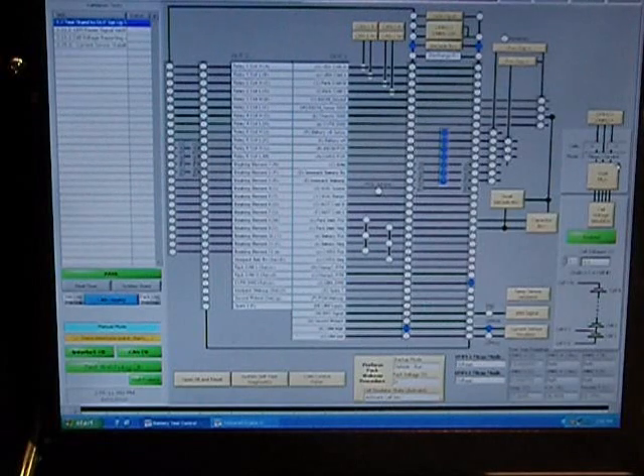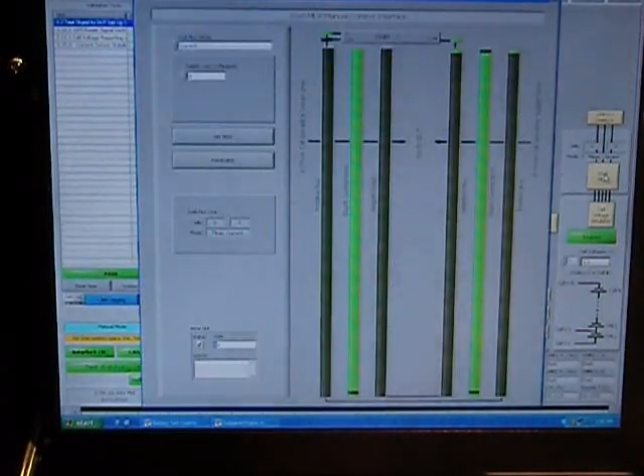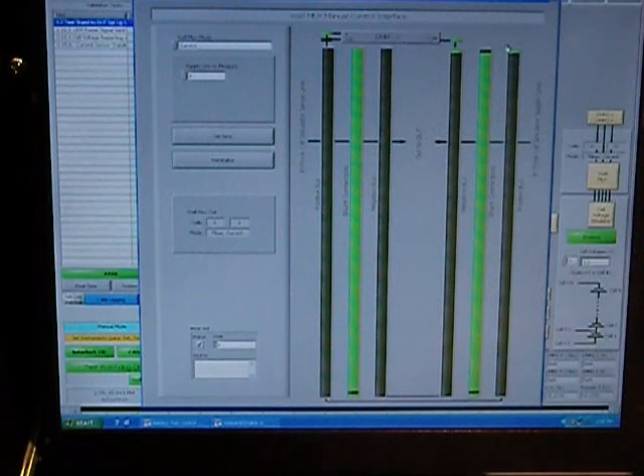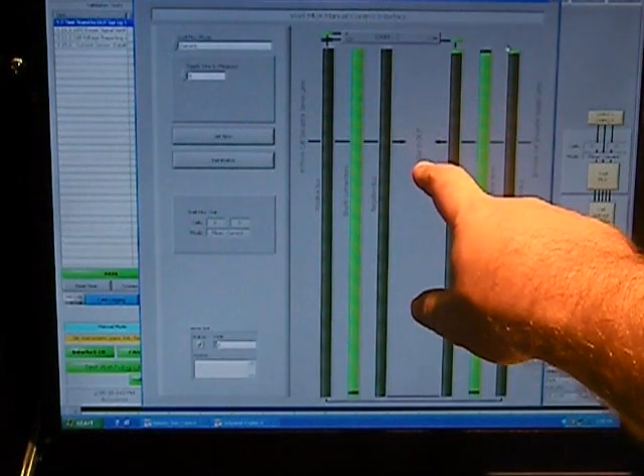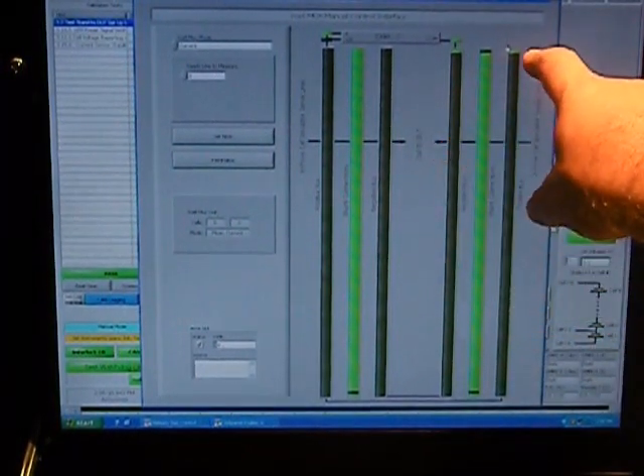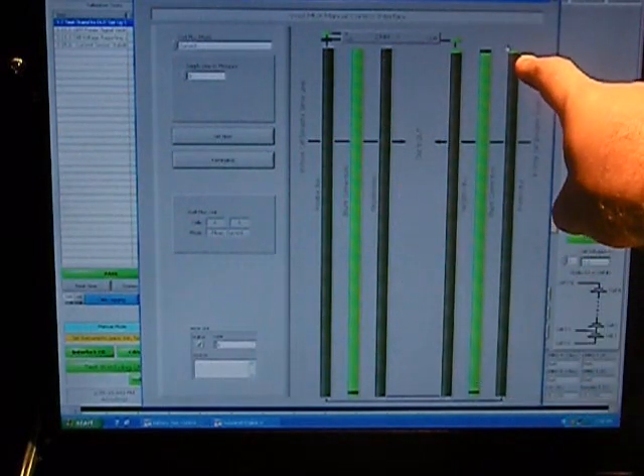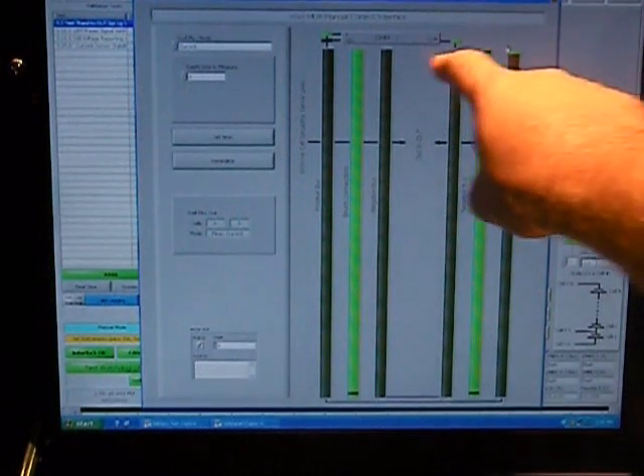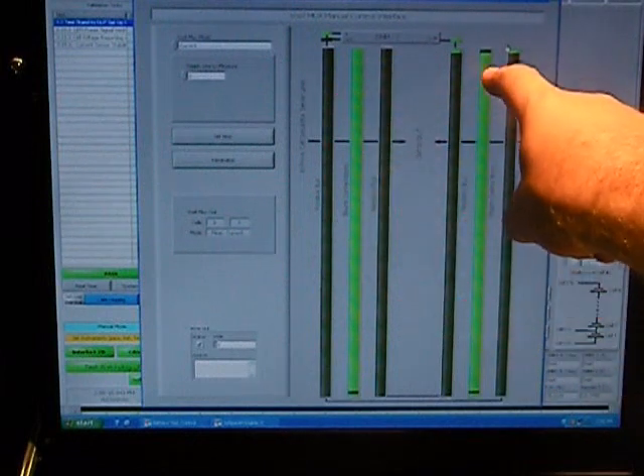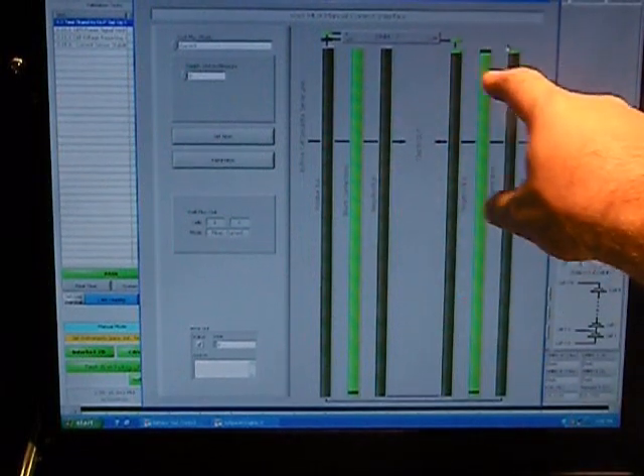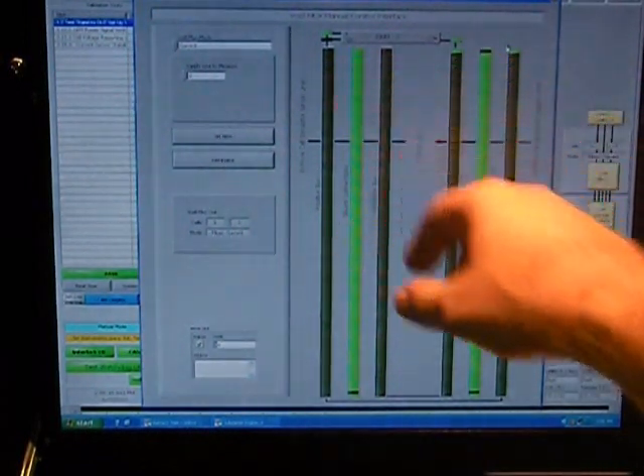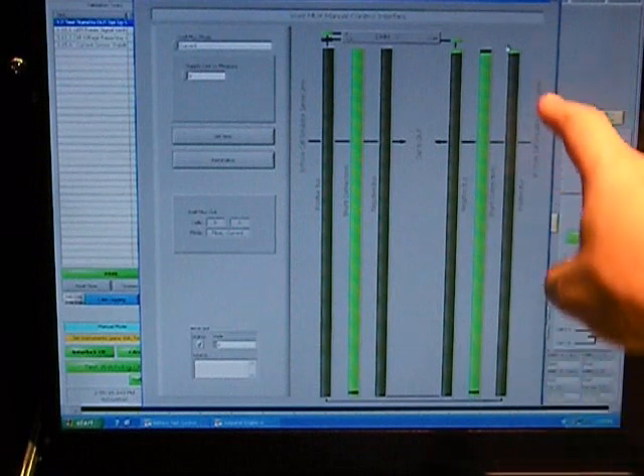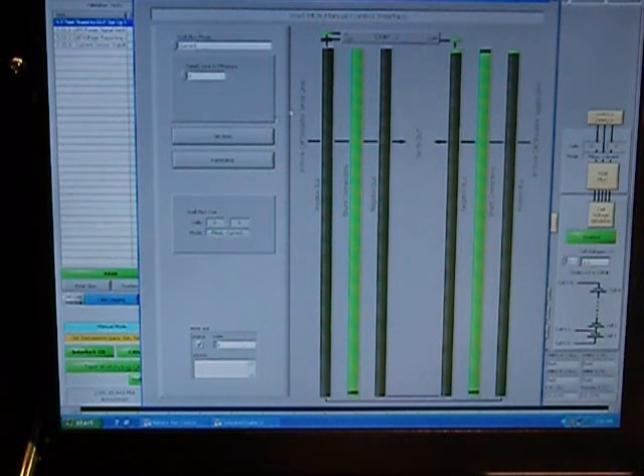So another interesting measurement that we can make with this arrangement is to set our multiplexer between the battery cell stack simulator and the BMS under test. We can set this relay system to measure the current on a particular supply line. So you can see in this case we've closed these two outer relays which force current through the digital multimeter inside the PXI chassis out to the product, and on the rest of the lines we have a shunt relay or bypass relay closed so that those cells go directly through from the simulator to the product.